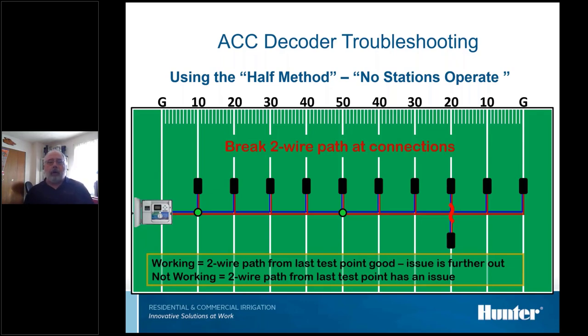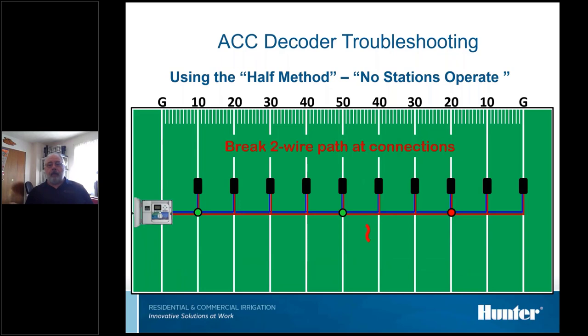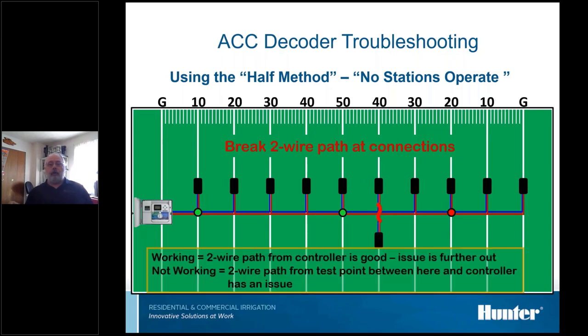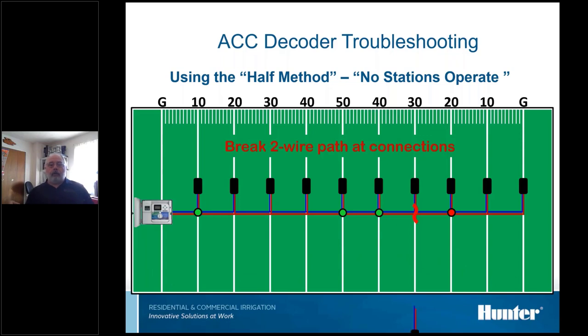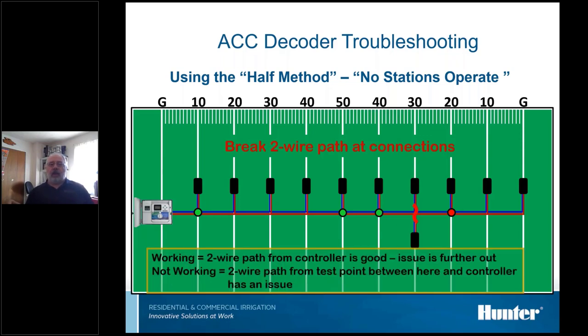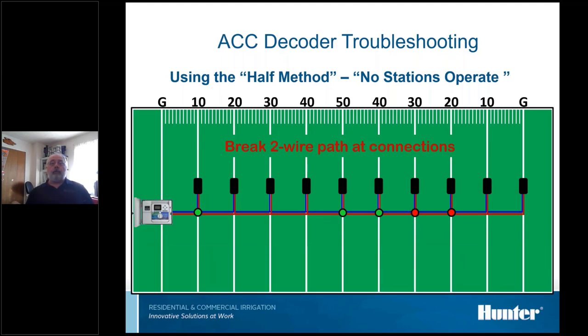If we go halfway out or thereabouts again, do the same thing. Okay, it didn't work at that point, so we went past our problem. And now it's back up. And Murphy's Law says that the first one would be good, and it's got to be this one. And it was. So you would just replace that decoder, cut that decoder out, test, and then replace it. So that's how the half method works.